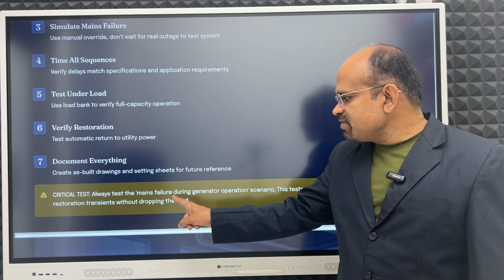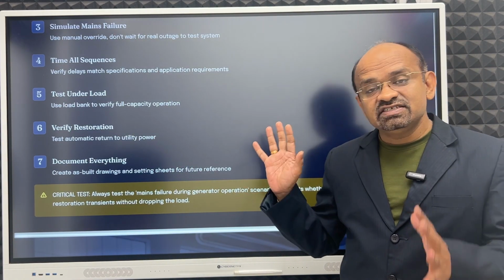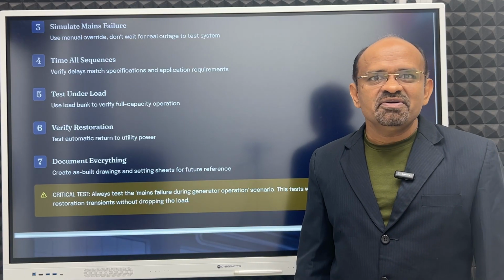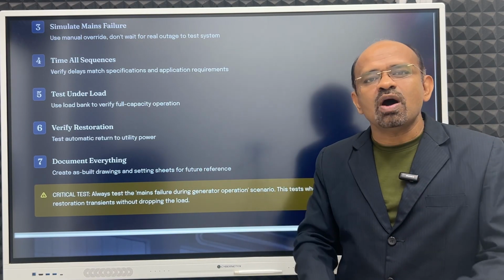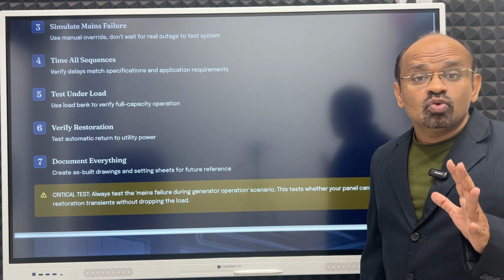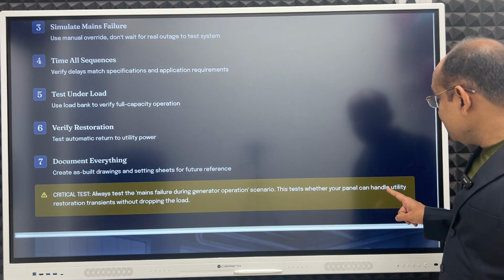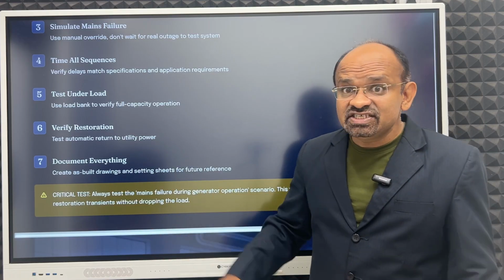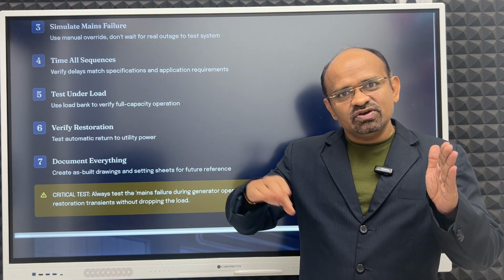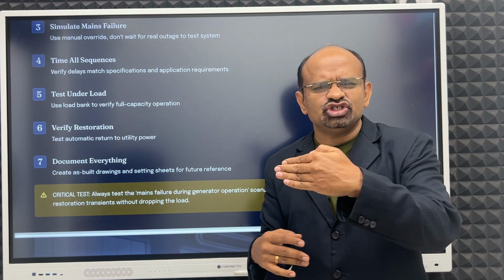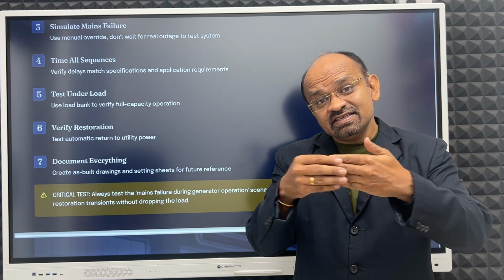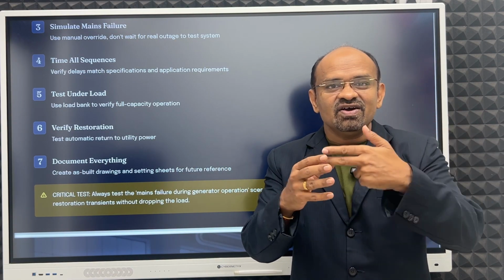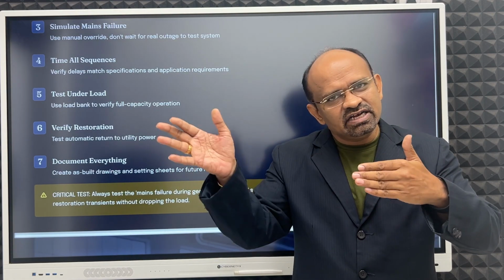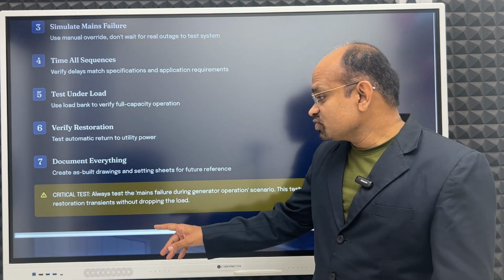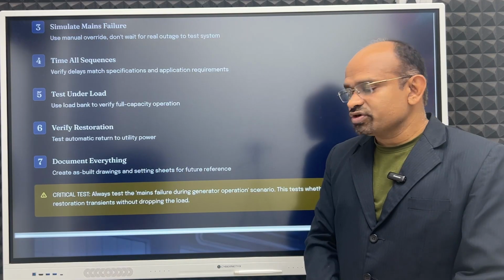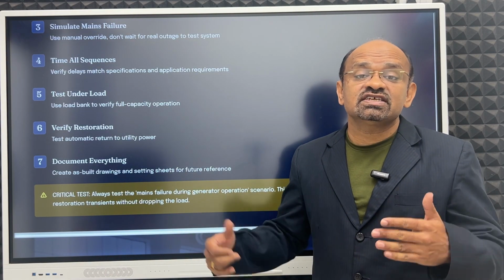Now, critical test. Always test the mains restoration during generator operation scenario. When the generator is working, at that time you should switch on the mains from the city power so that the generator should stop and give back the load to the city power. Now why is it important? This tests whether your panel can handle utility restoration transients. We have seen in water also there are transients, waves at the start, inrush. At inrush the current will be high. Then this resistance, we have seen the stones in the water current; in the same way, this resistance is the stones in the water current. It will restrict the current flow. So inrush currents will be there, and it should sustain the transients without dropping the load.